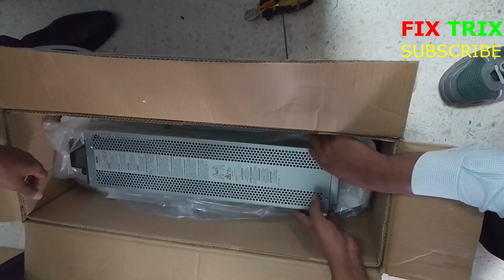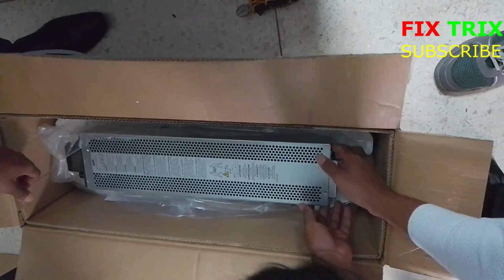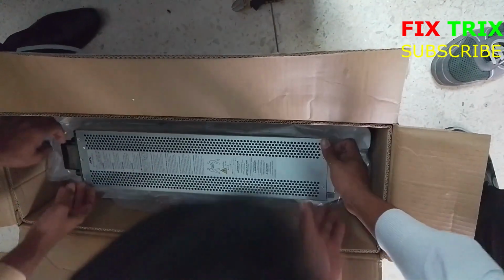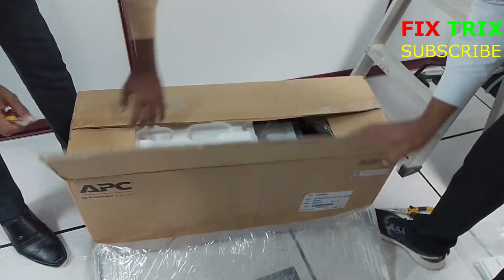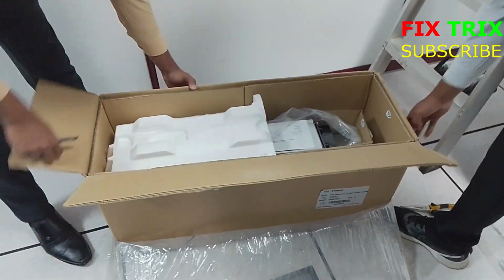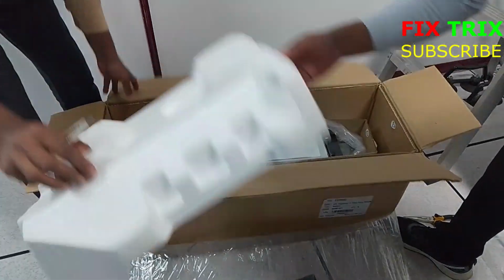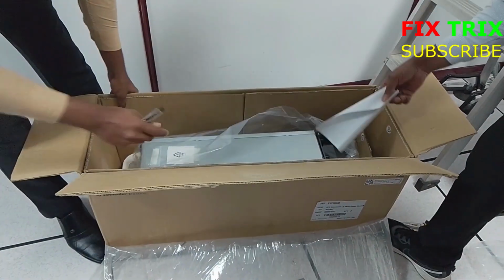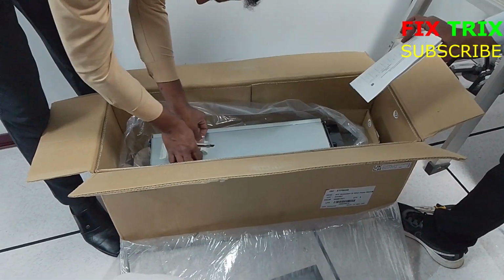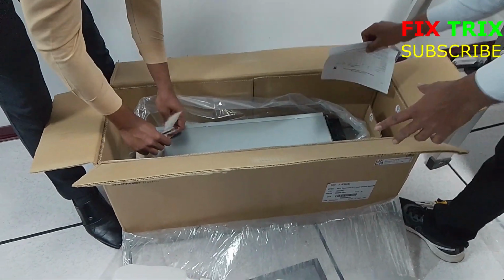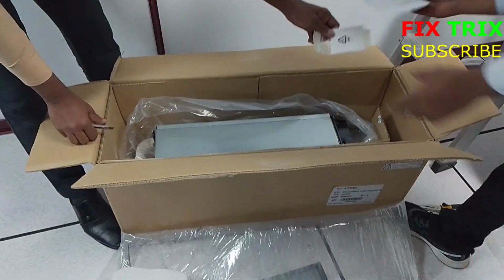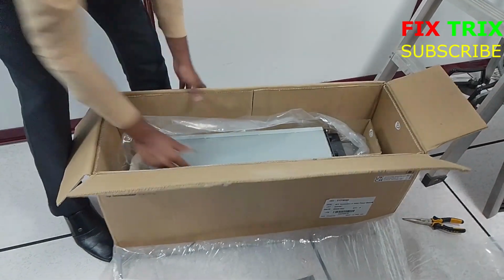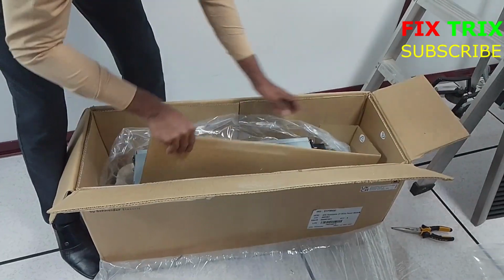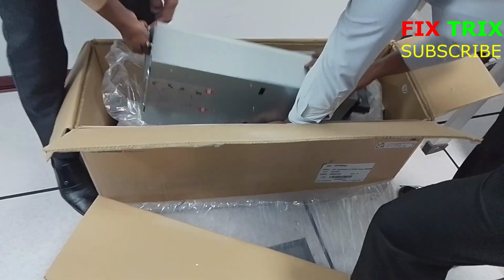In this video, you will see correct power on sequence, input circuit breaker and maintenance bypass explanation, battery module switch on, installing remaining power and battery modules, running self-test, setting date and time, final system checks. By the end of this video, the UPS will be fully operational. In this step, we will unbox all remaining power modules and battery modules.